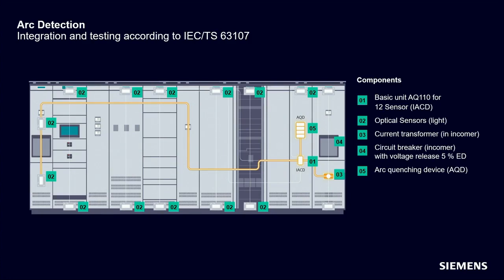Such a system usually consists of a detection relay, light sensors, current transformers, a circuit breaker, and an optional quenching device. The light sensors are installed in different areas of the switchboard and monitor for light emission from an arc fault. If a light event is detected, a signal is sent to the detection relay, which sends a trip signal to the circuit breaker of the incoming feeder. To avoid false triggering by other bright events, the sensors are precisely matched to the spectrum of an arc fault, and current transformers provide an additional triggering criterion — a steep rise in current must also be detected before the trip signal is sent.